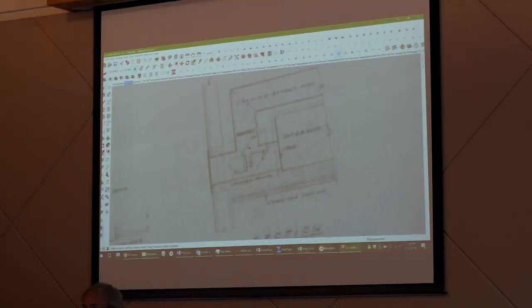which you can do. Isn't that amazing that we can do that? And you still see there's a resolution problem. But you can read this close enough. At the zone, you had a hot duct and a cold duct with an actuator and a pair of dampers. And basically, as you close the cold damper, you open the hot damper and vice versa. There's no flow regulation. It was just a pure temperature thing. Big old low pressure system.